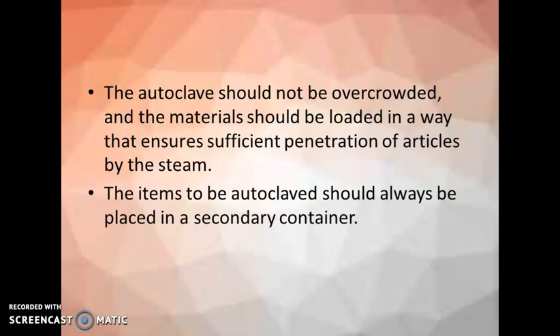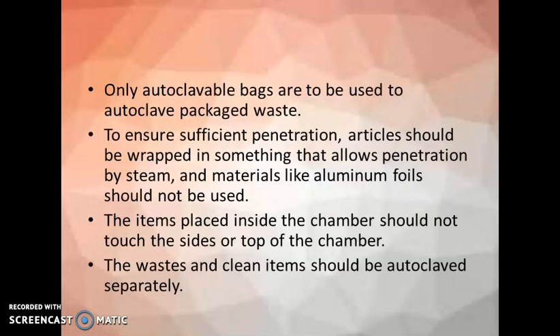The autoclave should not be overcrowded, and the material should be loaded in a way to ensure sufficient penetration of articles by the steam. So it should not be overloaded. The items to be autoclaved should always be placed in a secondary container, not directly. Only autoclavable bags are to be used to autoclave packaged waste. So the packaged waste is usually placed inside the autoclave in autoclavable bags. To ensure sufficient penetration, articles should be wrapped in something that allows penetration by heat and steam. Materials like aluminium foil should not be used in the autoclave. These aluminium foils are usually used in a hot air oven.